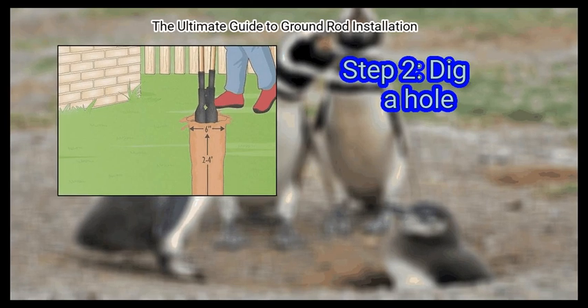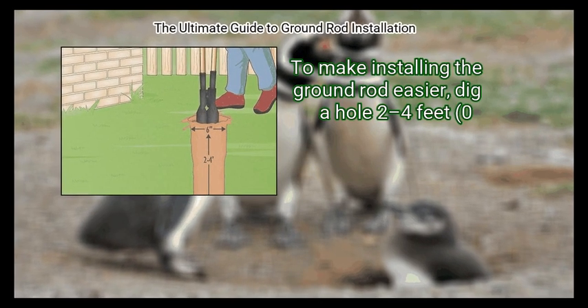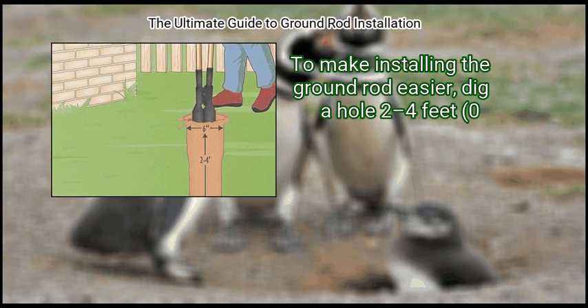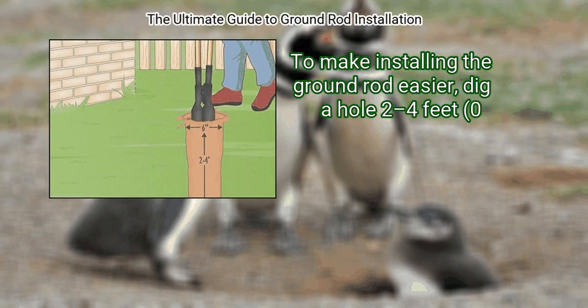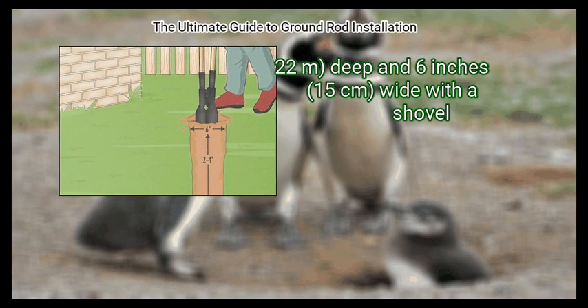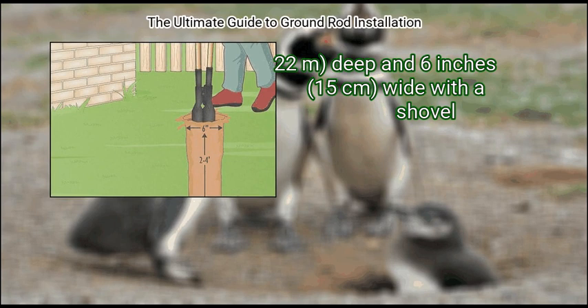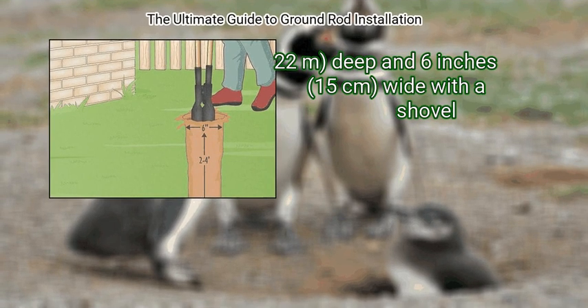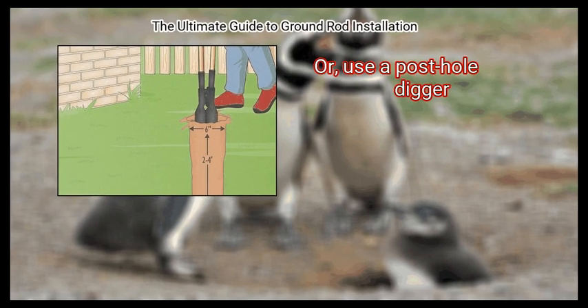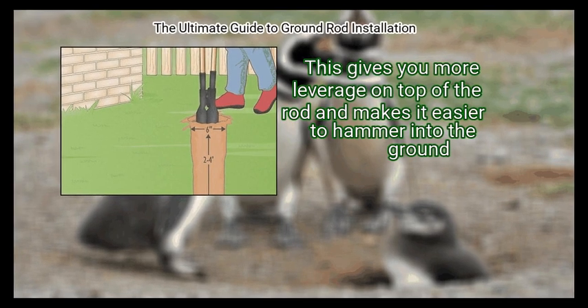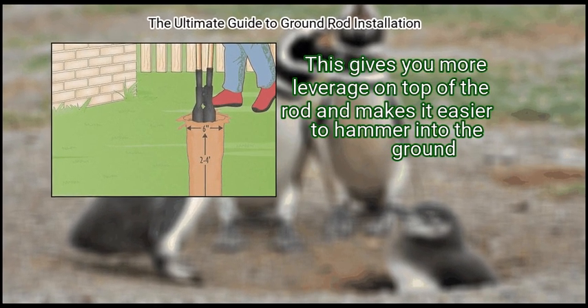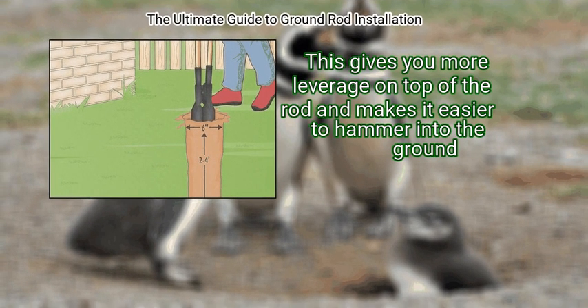Step 2. Dig a hole. To make installing the ground rod easier, dig a hole 2 to 4 feet, 0.6 to 1.2 meters deep and 6 inches, 15 centimeters wide with a shovel. Or, use a post hole digger. This gives you more leverage on top of the rod and makes it easier to hammer into the ground.